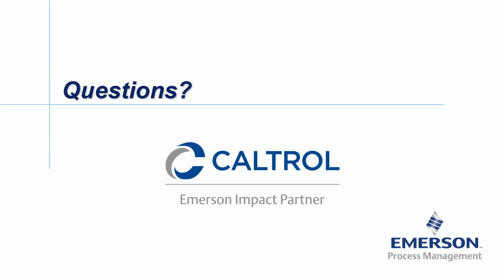Anything where you have redundancy and they rotate back and forth, a quarterly vibration program on those assets is fine, because half the time we have to have an operator start up the lagging equipment that's not online. If you have a good rotation program, a lot of customers use our reports for their rotation. So we send them a report and they see that the secondary water pump wasn't running. Well, okay, let's have that one running, and now the other one's down the next time that we come out. So you're continuously getting data on all assets.